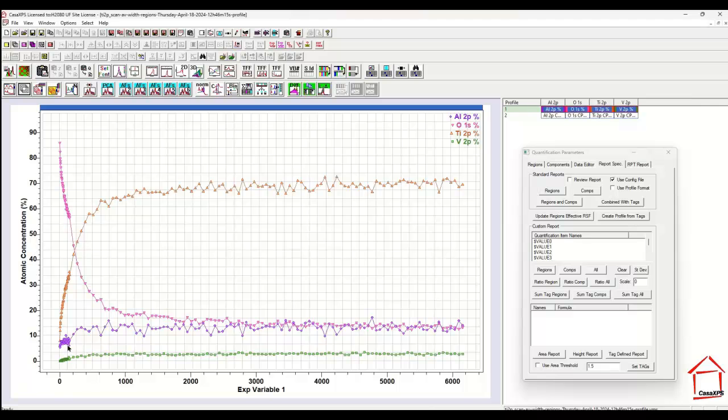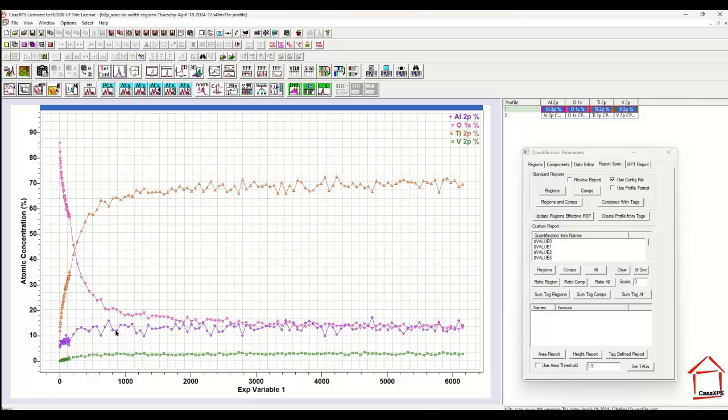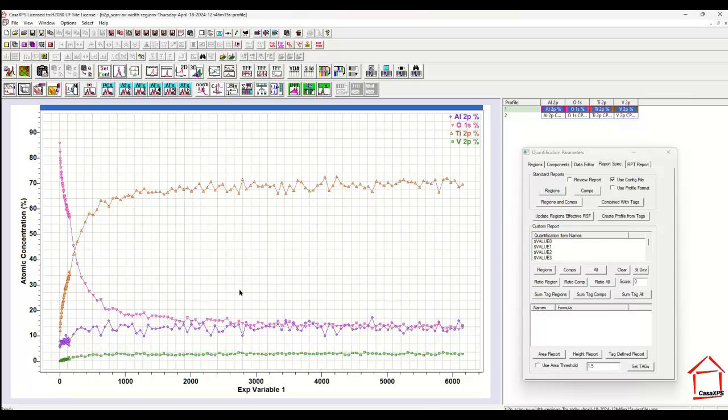We can see this probably slightly better if we do some display adjustments. And what we see is quite an unstable form for the aluminium trace. We see lots of variation and this even with the average width is a consequence of the noise in the data. And by virtue of the fact that we are using the aluminium signal as part of the calculation of these atomic concentrations, they all contribute to the denominator, that noise within the aluminium can also be amplified and entered into these other traces.